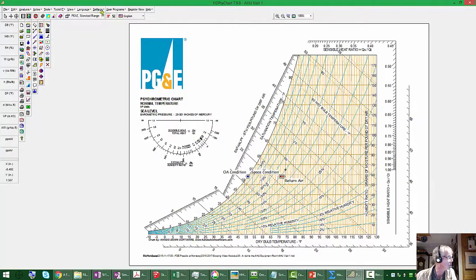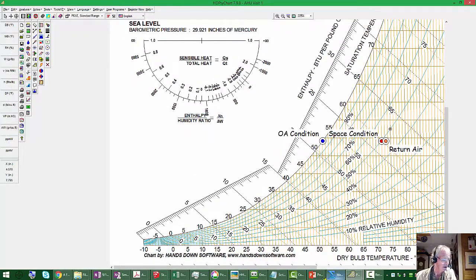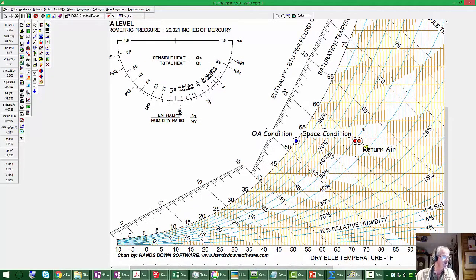And so I'm going to zoom in on this a little bit so you can see it a little better. And the way we measure the energy of the air is by this enthalpy parameter. Enthalpy sounds sort of scary and woo, but it just is a word that means internal energy, and of H equals U plus PV, internal energy and flow work. We really don't need to get in that, but for the purposes of our discussion, if you know the enthalpy of the air, you know the energy content, both in terms of the sensible energy and the latent energy, the energy that's keeping the water in a vapor state. And so if you can read the enthalpy just by, there's a number of ways you can do that.